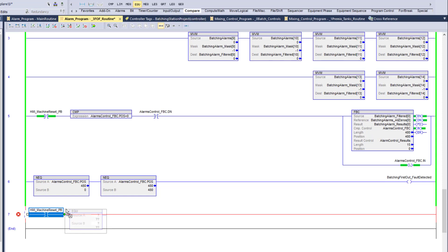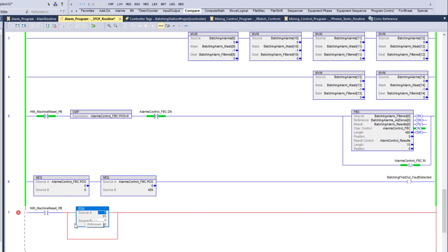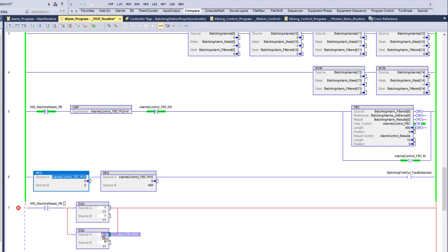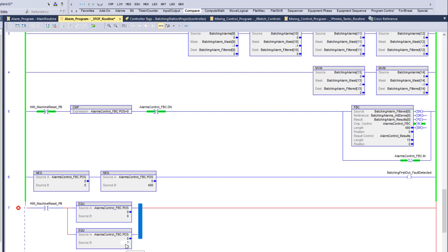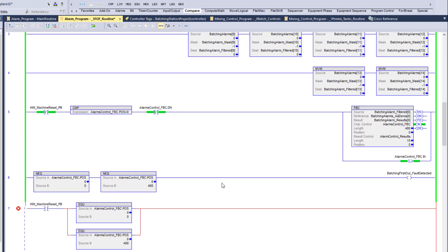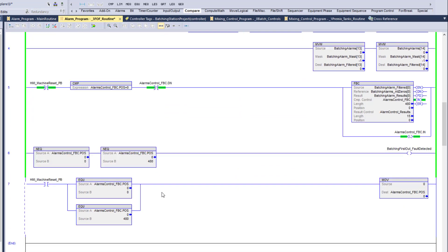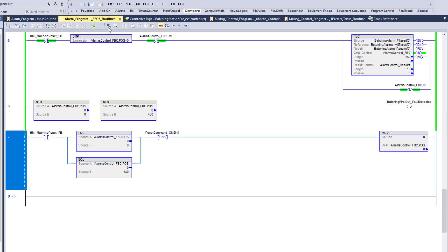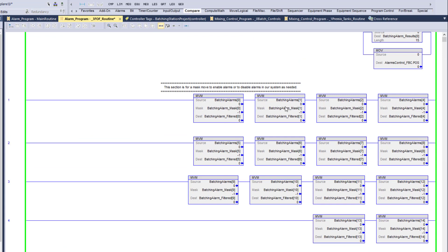The goal is to learn multiple ways of doing things. We'll copy the EQU instructions, grab the position, and say the position is equal to zero or 480. If it meets that condition, we paste the move down here. We also paste a one-shot in there so you're guaranteed everything will 100% go through and reset.